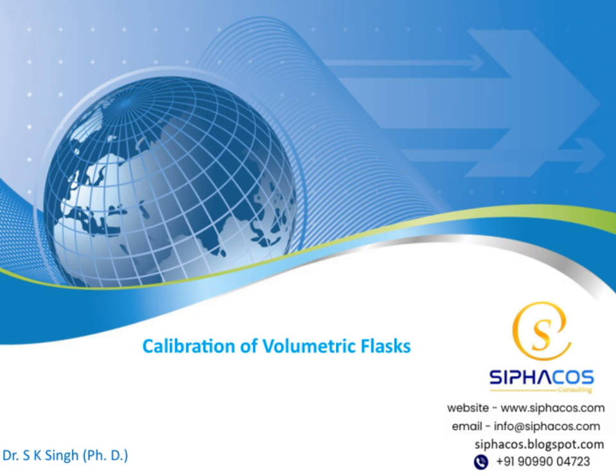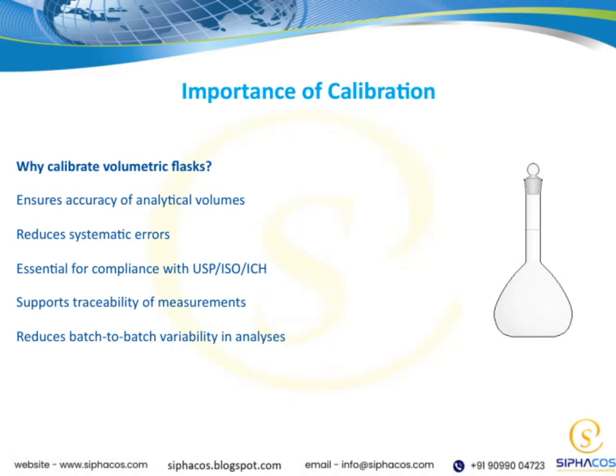Let's get started. Let's talk about why calibration of volumetric flasks is so important. First, calibrating them ensures the accuracy of the volumes we measure, which is crucial for reliable results. When our measurements are accurate, we reduce the chance of systematic errors that can skew our data. This is especially important when we need to meet strict standards like those set by USP, ISO, or ICH.